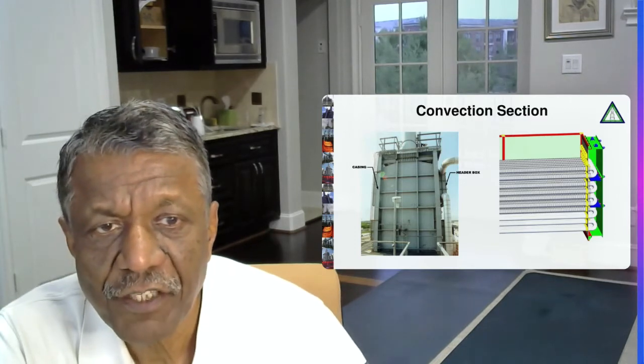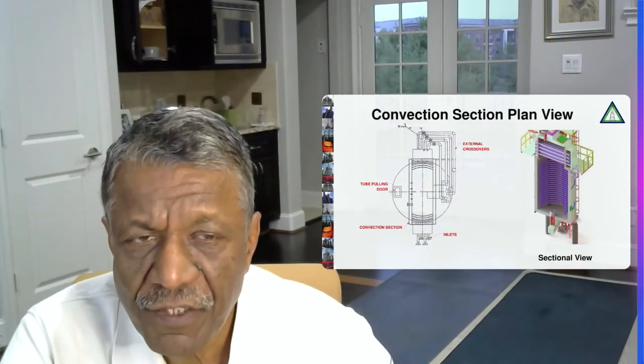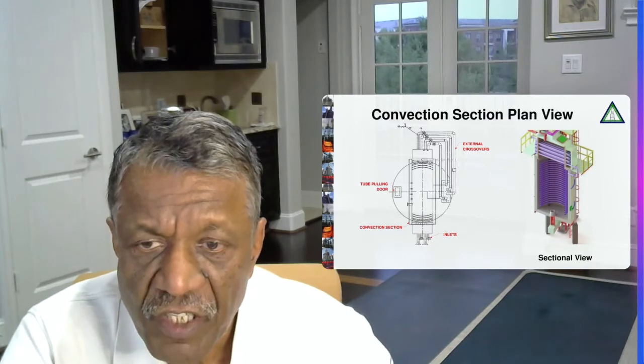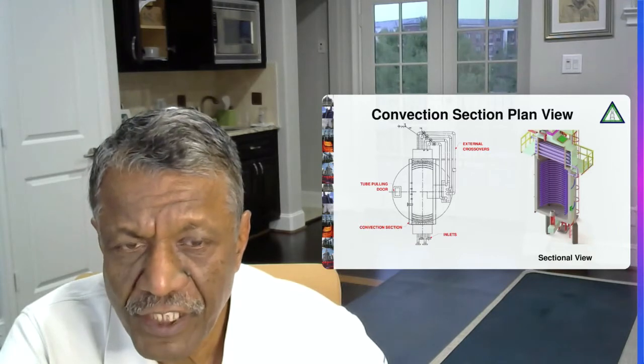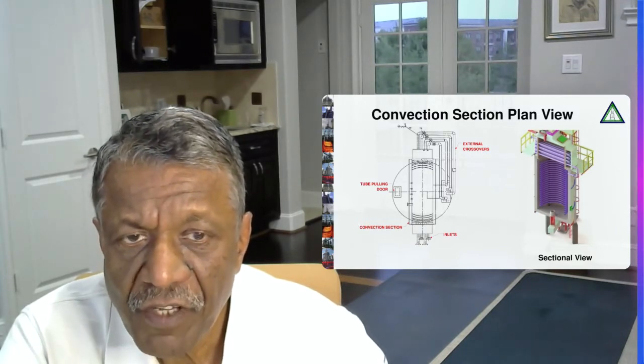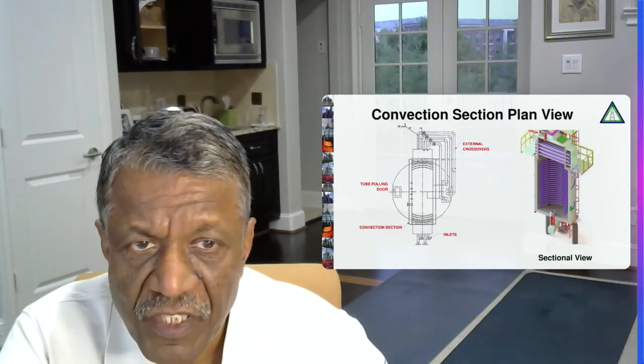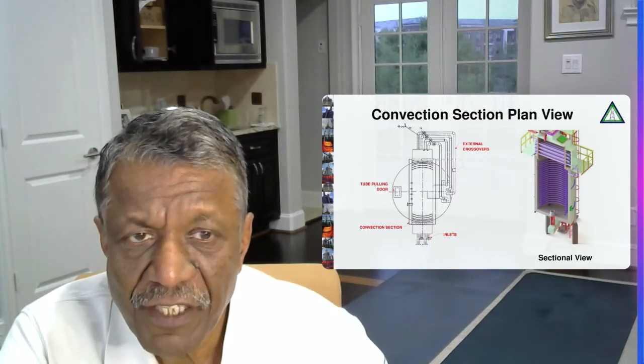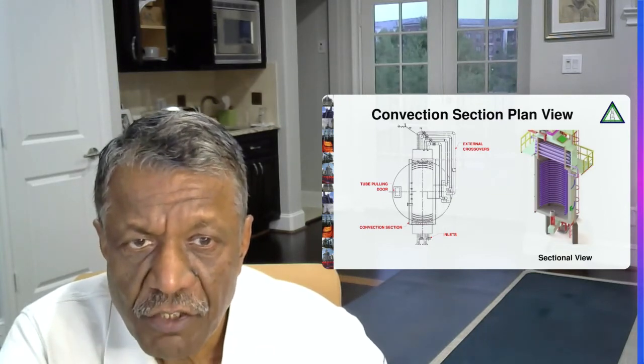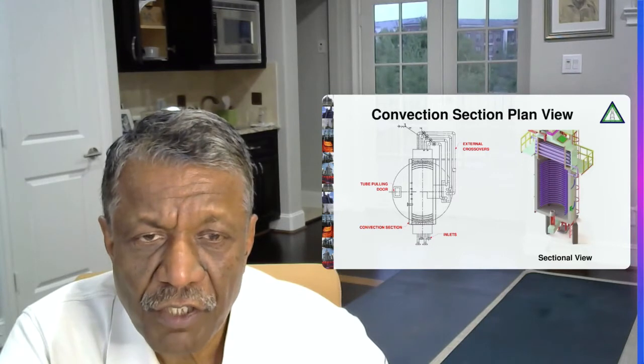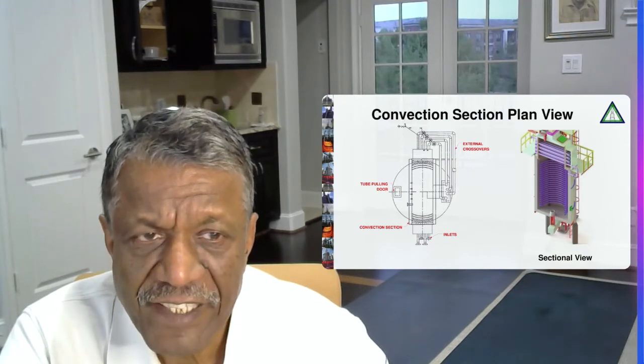You can see the casing, you can see the header boxes in the picture. This is a plan view of a convection section for again a vertical cylindrical heater. Feed generally enters the convection section because it is cold over there. And once it is heated, then the fluid is transferred from the convection section to the radiant section. That transfer takes place through the pipes which are known as crossovers. External crossovers are generally used nowadays. You can also see a tube pulling door for the maintenance purpose or for removing the tubes if they get damaged.